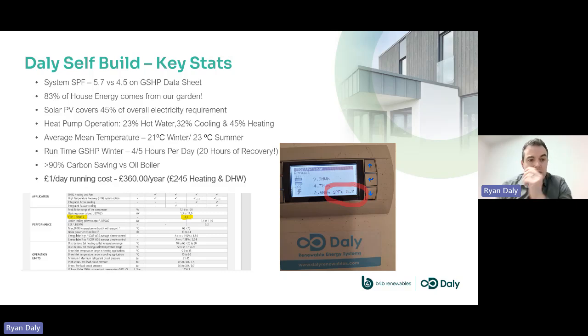In our first year when I monitored the system, 45% of our overall electrical requirement was covered by our PV array, which is a 3.6 kilowatt inverter on the garage and 5.3 kilowatts of panels on the roof. Our heat pump operation, when you broke it down for last year, is 23% hot water, 32% cooling operation, and 45% heating operation. The average mean temperature is 21 degrees in the winter in our house and 23 degrees in the summer. And the run time for the heat pump is around 4 to 5 hours per day on a cold day.